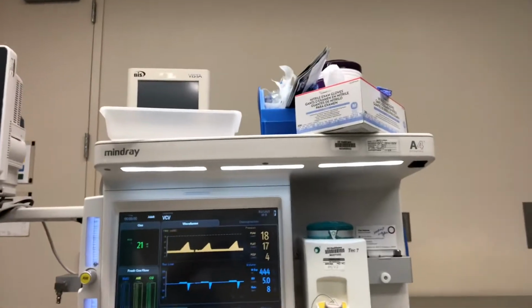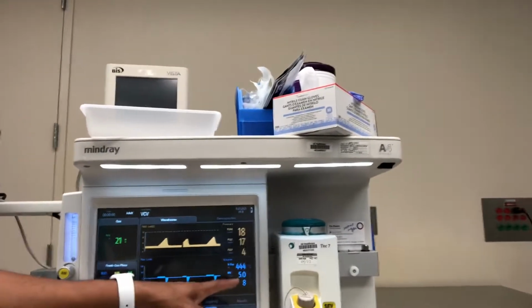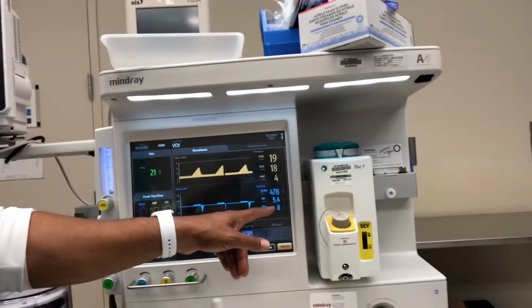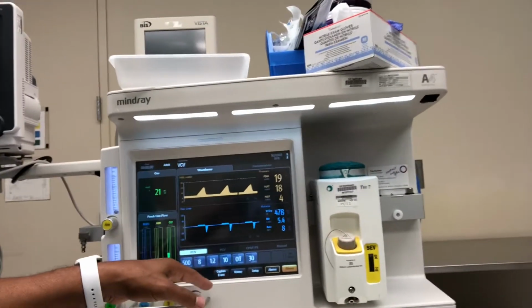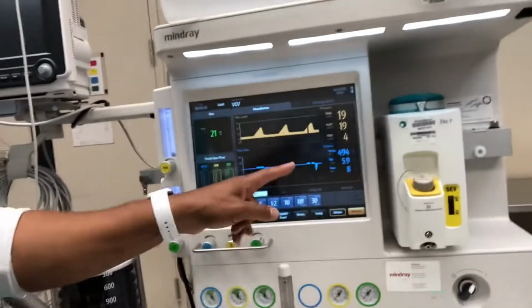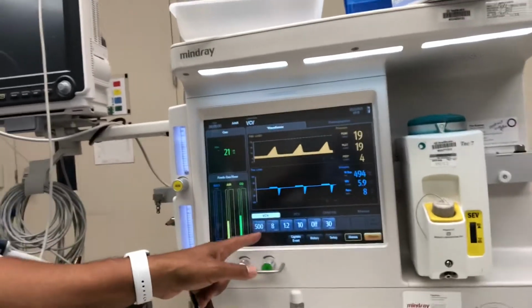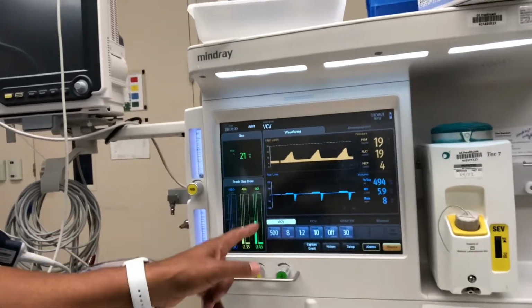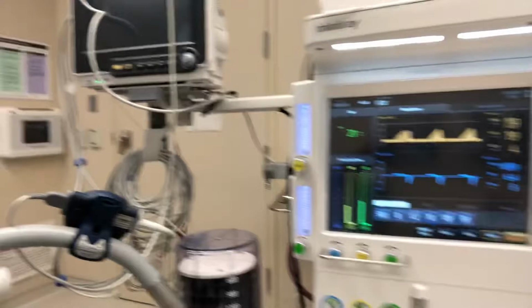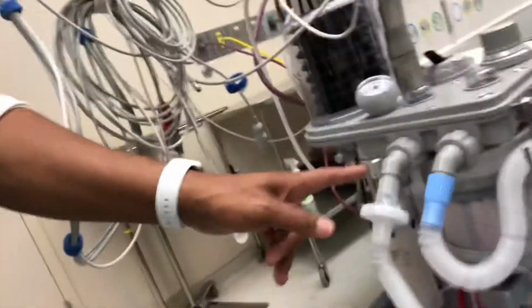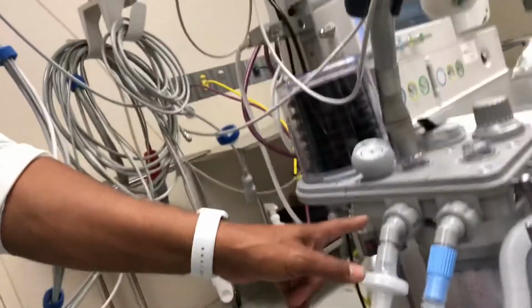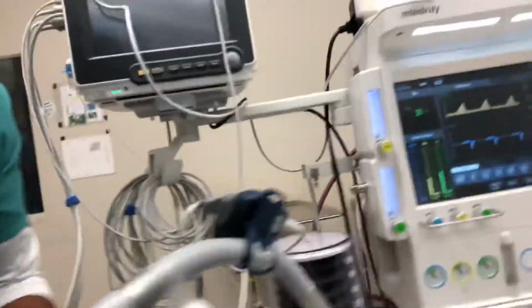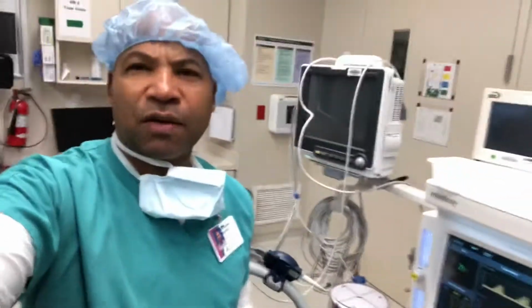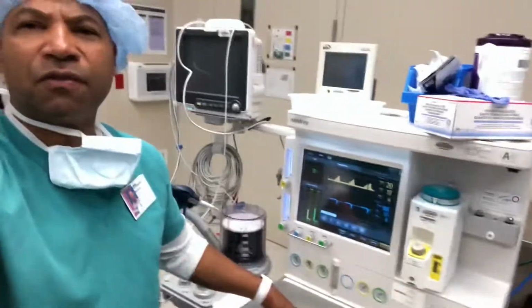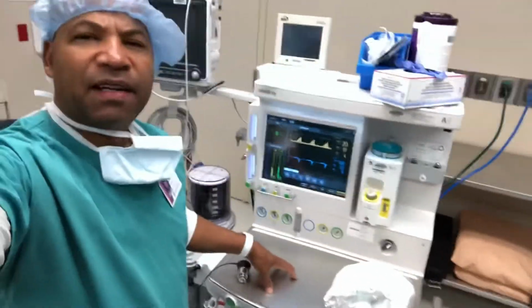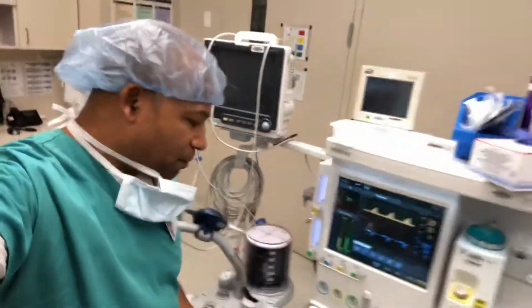We have our volumes around 500 VT. We have expired volume right now, 478, which is good and is climbing, which is fantastic. Our tidal volume is 494, dialed in 500. That shows me our flow sensors are operating. If we're having a problem with that, we want to check our flow sensors again, either calibrate them or we might have to replace them. So again, these are just quick tips. I encourage you to follow the procedure manual for the Mindray units, but if you're not too familiar with them, wonderful machine, and I would encourage you to spend more time learning it.